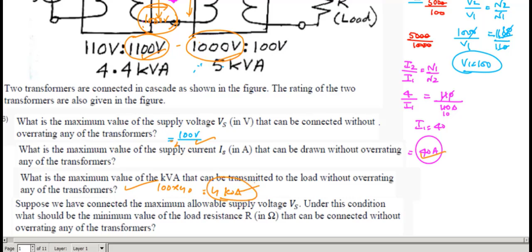We know the voltage is 100 volts, and without overrating, the current is 40 amperes. So what is the maximum kVA? 100 into 40 equals 4 kVA, which is the maximum value that can be transmitted to the load without overrating the machine.